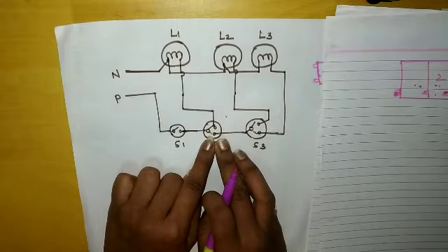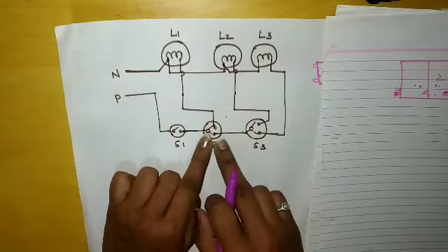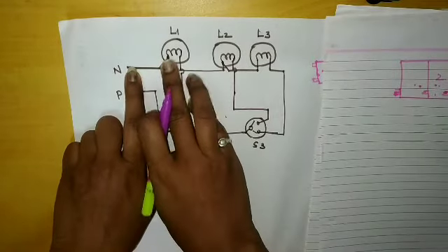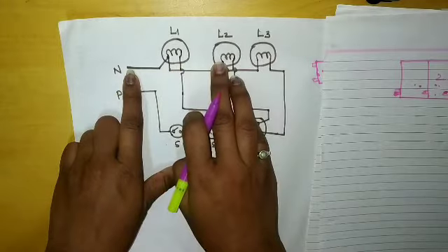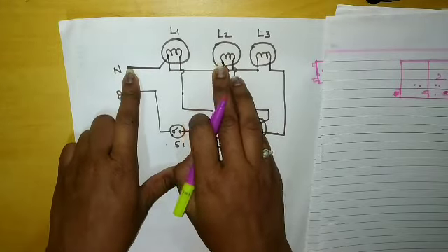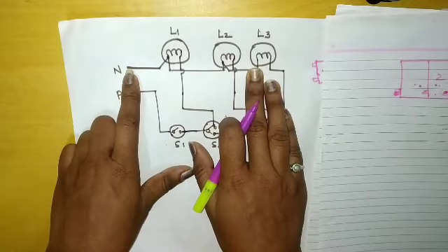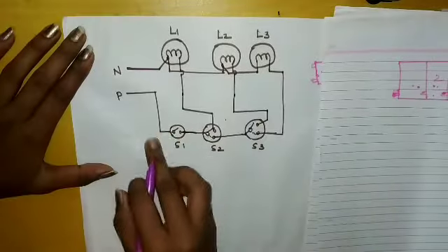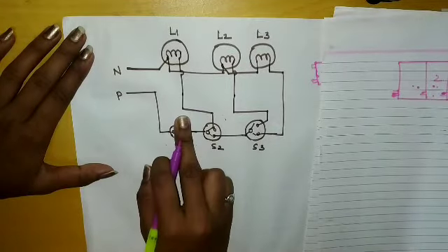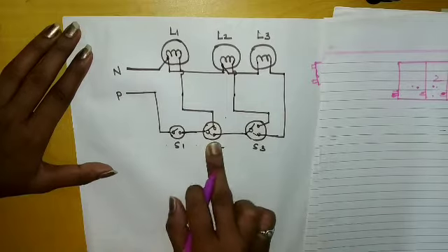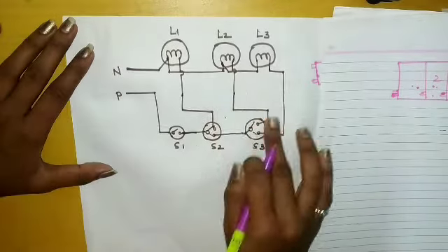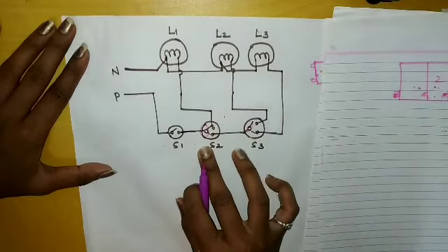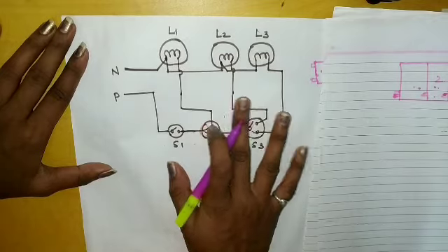the two-way switch that we have used to control staircase wiring. We have to use it here. So the wiring is similar. Here neutral is linked or given first to lamp 1 and then linked to L2, that is bulb L2, lamp L2, and from that it is given further to L3. And then to complete this circuit, the switch S1 and this lamp L1 are connected to this S2, that is the two-way switch, and the wiring is done similarly. So these are the common points of the two-way switch. So this is the diagram of godown wiring.